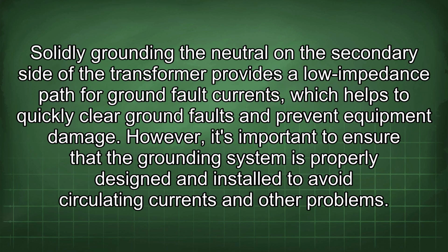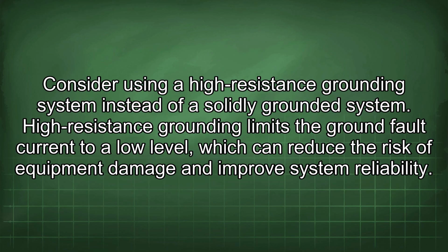Solidly grounding the neutral on the secondary side of the transformer provides a low impedance path for ground fault currents, which helps to quickly clear ground faults and prevent equipment damage. However, it's important to ensure that the grounding system is properly designed and installed to avoid circulating currents and other problems. Consider using a high-resistance grounding system instead of a solidly grounded system.